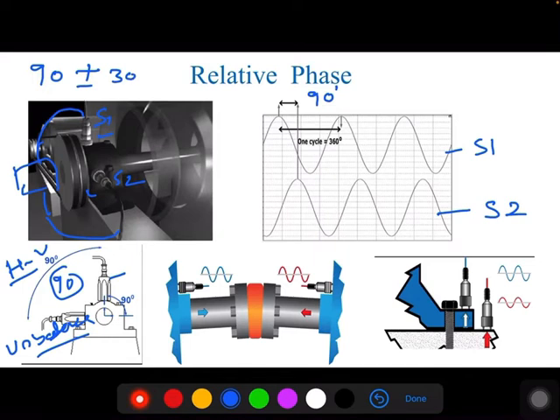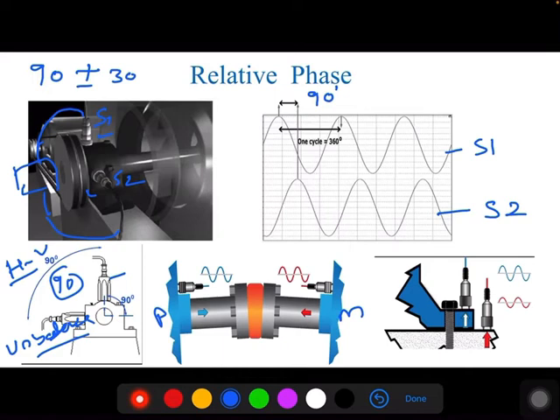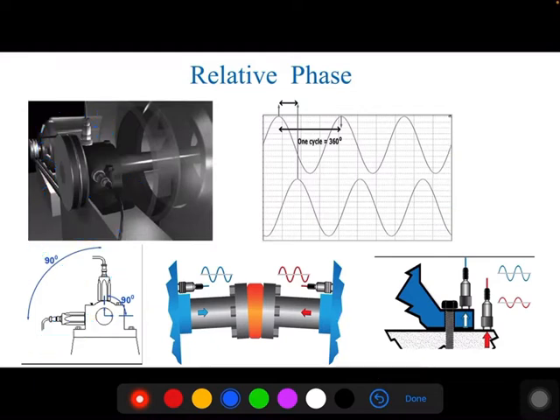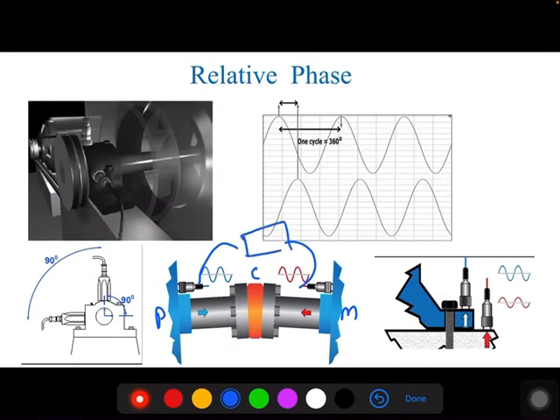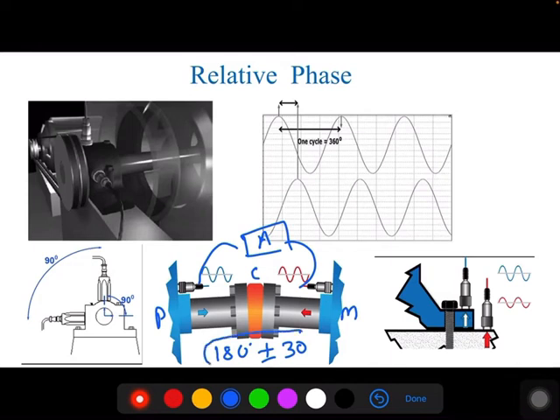For a pump and motor connected by a coupling, if there is misalignment between them, place one sensor at the pump bearing and one at the motor bearing across the coupling. If the phase difference between the pump and motor signals is around 180 degrees (±30 degrees), then there may be a misalignment.